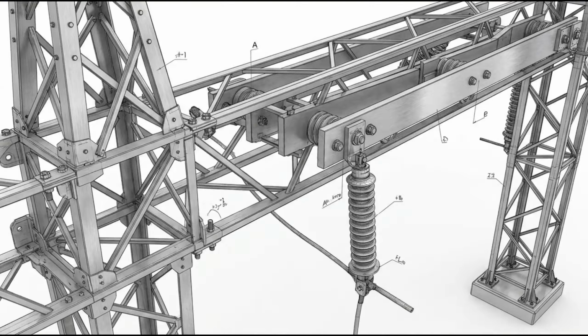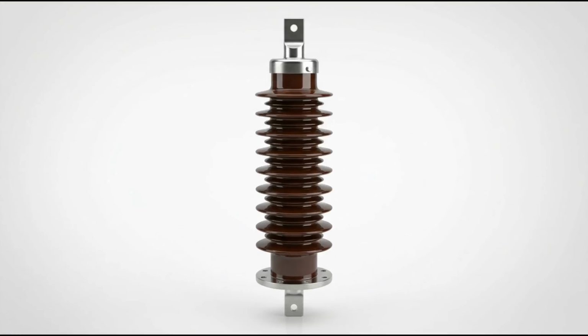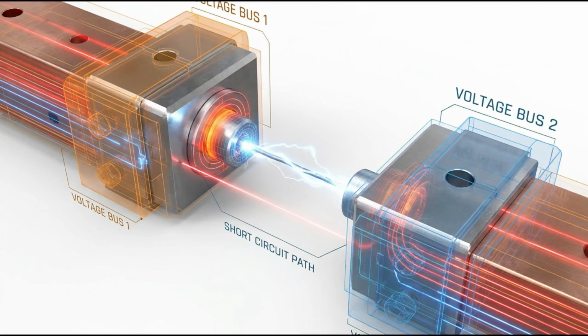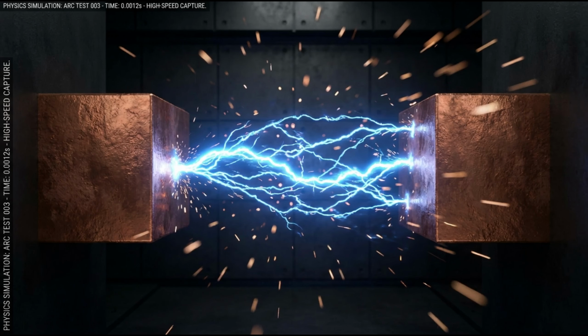To understand why substations are uniquely vulnerable, we must look at the physics of open-air electrical insulation. High-voltage transmission substations rely on physical air gaps to isolate phases operating at hundreds of thousands of volts. A drone does not need to carry a heavy warhead to cause total destruction. By trailing a microscopic spool of conductive carbon fiber or thin copper wire, the drone bridges the air gap between two high-voltage busbars. The moment the conductive thread connects the phases, it creates an instantaneous phase-to-phase short circuit.